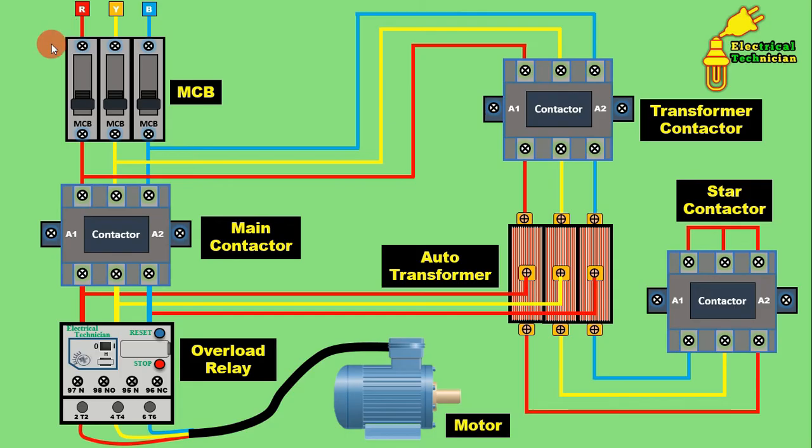To start the motor, first turn on the MCB. When the MCB is turned on, power supply flows to the incoming terminal of the main contactor and to the incoming terminal of the transformer contactor — but no contactor is turned on yet. When you press the start push button, firstly the star contactor turns on. The second terminals of the transformer are then shorted together — connected in star. Just after the star contactor turns on, the transformer contactor turns on, and power supply flows to the transformer. From the tapping, power supply flows through to the overload relay.